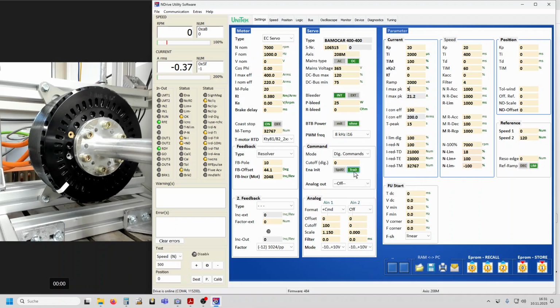This is very, very important for this test, because we want to enable on torque command with torque 0. So we just provide the back EMF voltage for the motor to run freely without any braking or accelerating torque. If you were enabling with speed control, the motor controller would try to brake the motor to 0 RPM immediately after initialization. But we do not want that. We want to have a torque-free, free-running motor when we enable the motor controller.